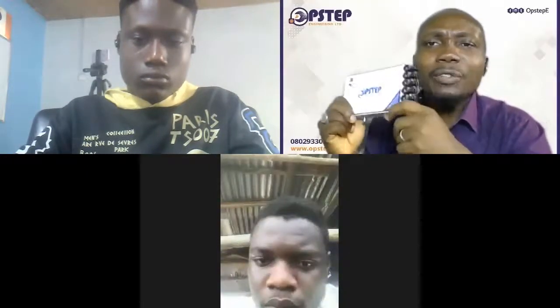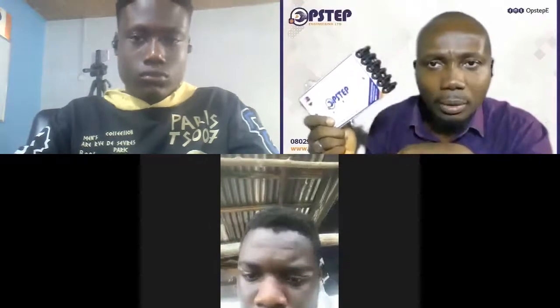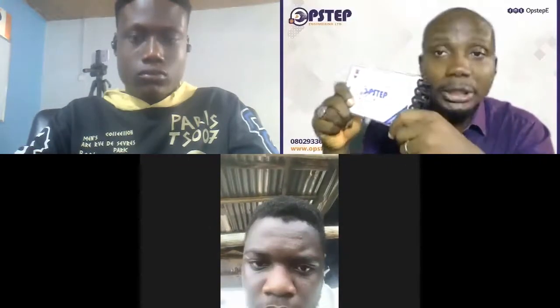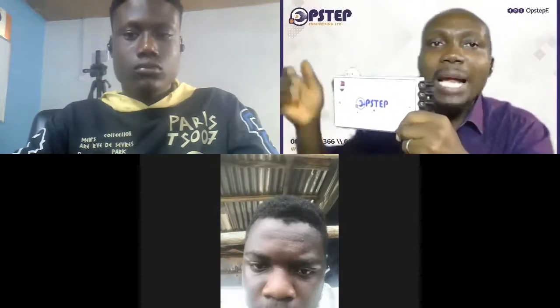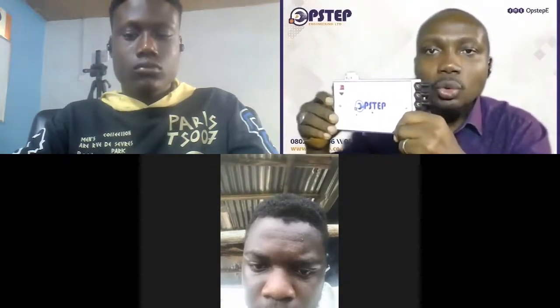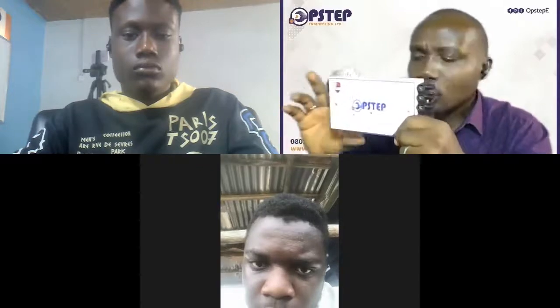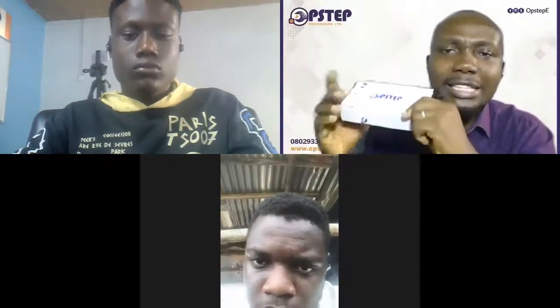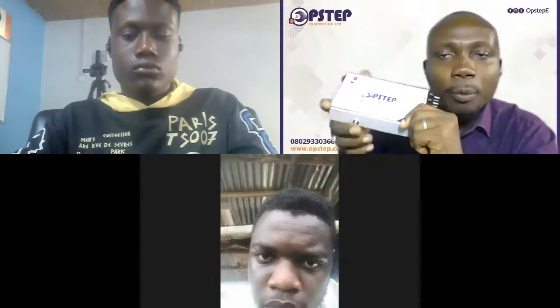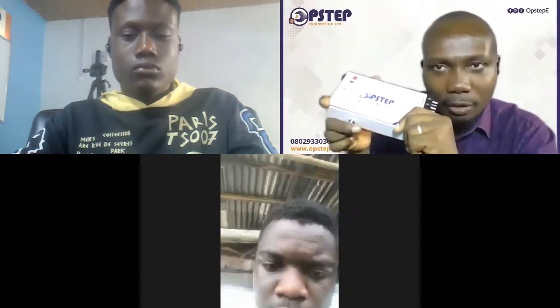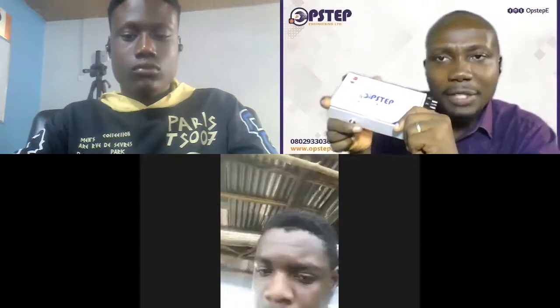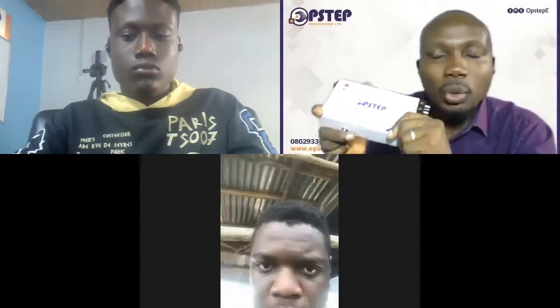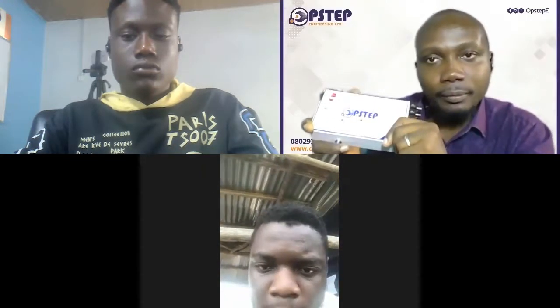Now, there's also the case of what if you've been running on generator and NEPA has not supplied you voltage and you want to turn off your generator. Instead of going out to where your generator is to turn it off, simple, you can simply hit this button. There is a button underneath this system that comes with it. If you press this button down long enough, between 2 to 5 seconds, up to 10 seconds, it will turn off your generator set for you.